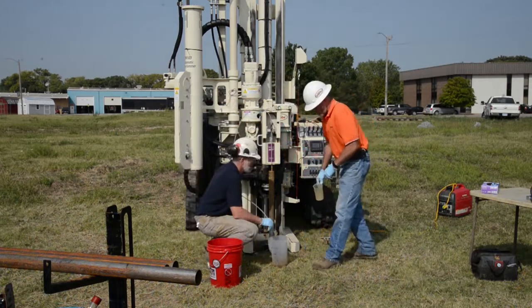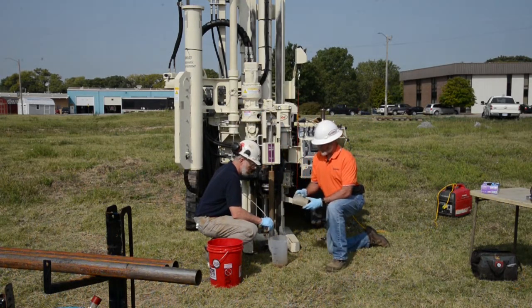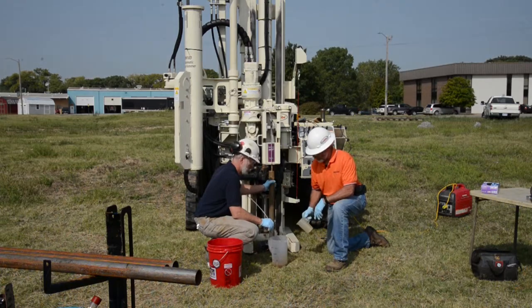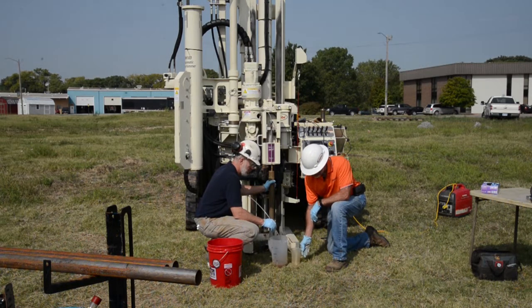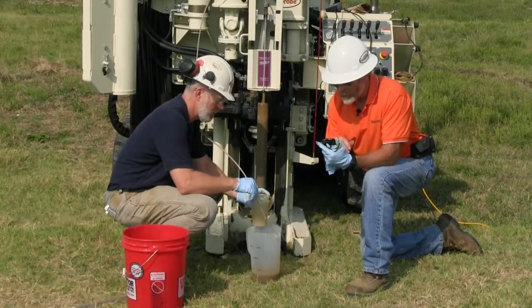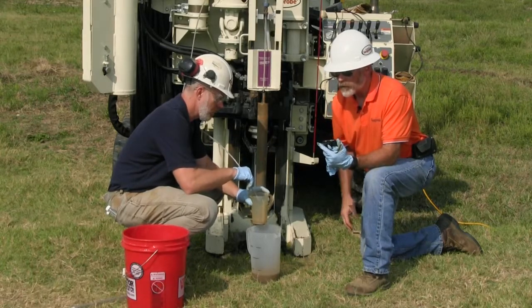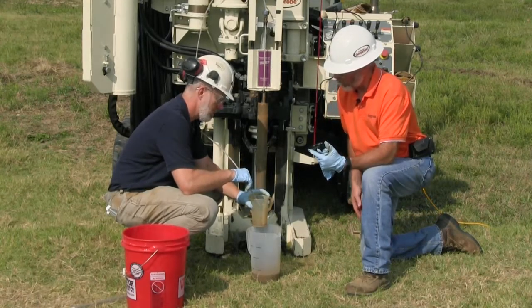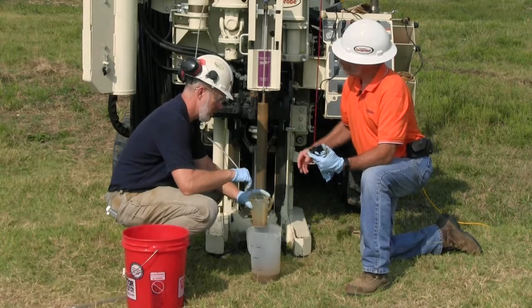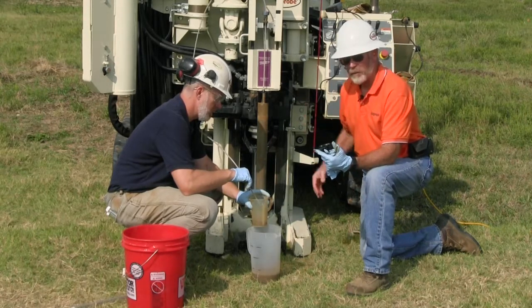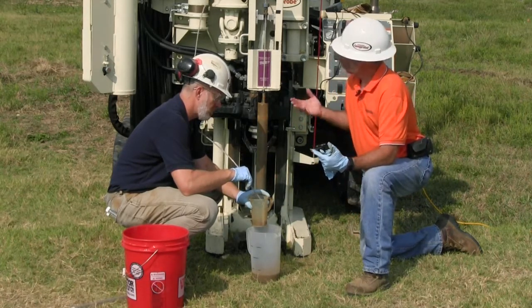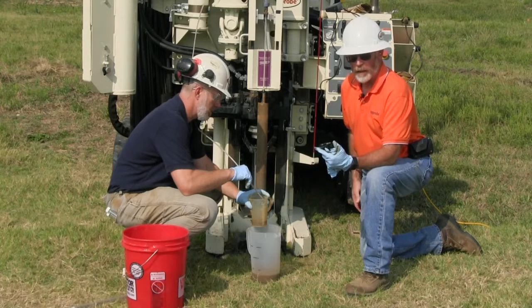Okay, so we'll check flow rate for you here. This is a 500 ml plastic beaker, and we'll just use this to check our flow rate. 1, 2, 3, go. Okay, so we're timing. We're just going to check our flow rate here. We're at a setting of 3, which is about half speed on the pump, roughly 60 cycles a minute, about 1 cycle a second.